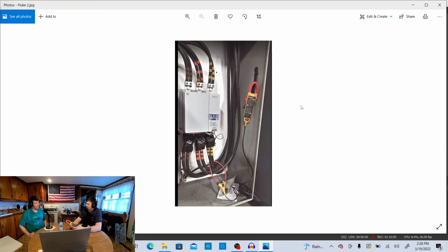So you aren't standing 2 feet away letting all that current run through. No, you don't want to do that, that's extremely dangerous. When a motor's getting going, take that 390 amps and times it by 6, that's roughly how much current could be coming through when it's trying to start that motor. So you can have a lot of electricity coming through at that point. Holy cow, that's a dangerous situation.